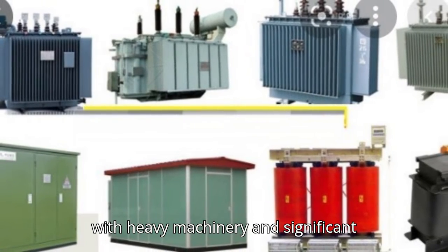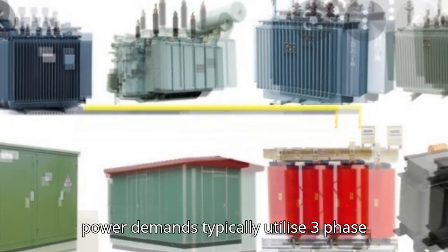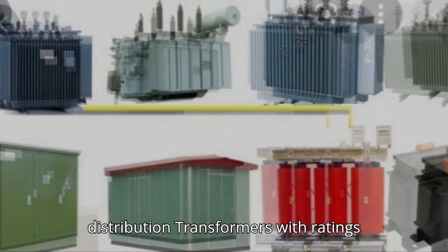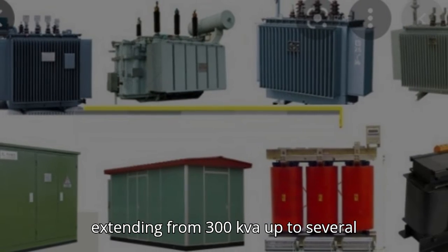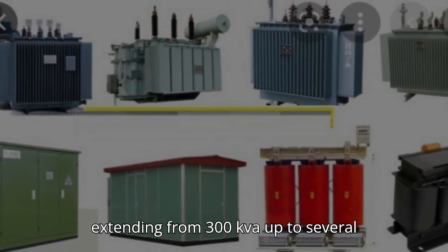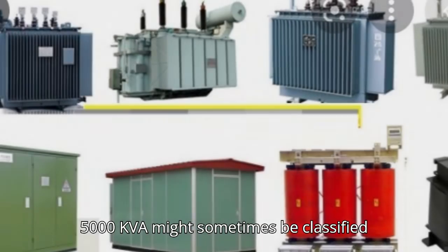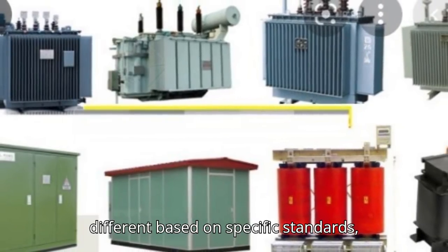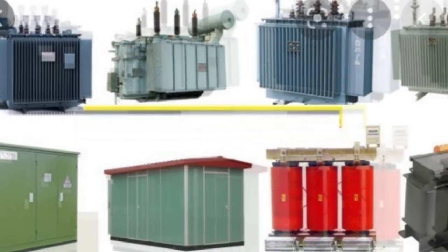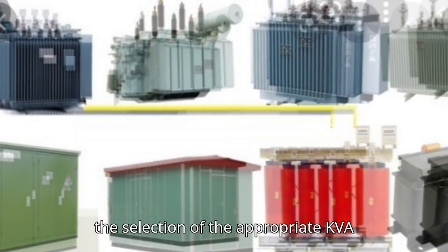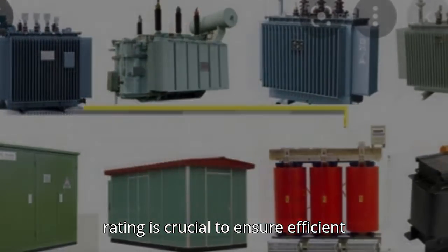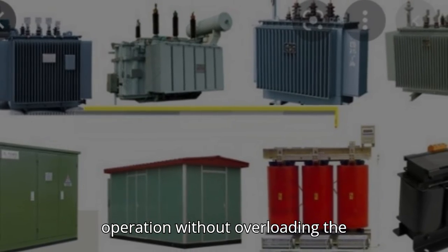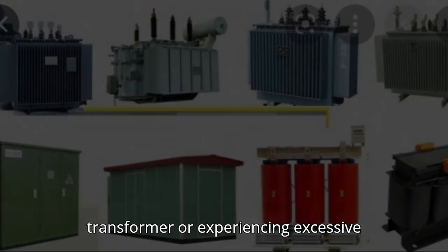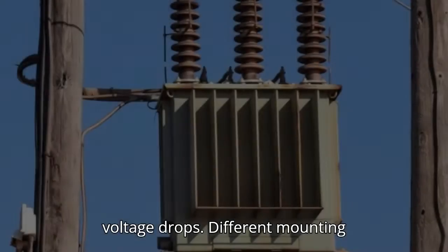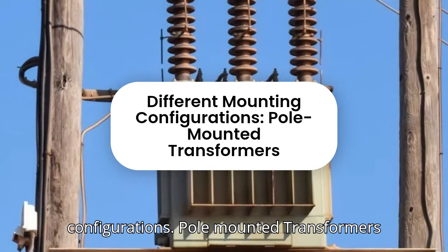Industrial facilities with heavy machinery and significant power demands typically utilize three-phase distribution transformers with ratings extending from 300 kVA up to several thousand kVA, although units above 5,000 kVA might sometimes be classified differently based on specific standards. The selection of the appropriate kVA rating is crucial to ensure efficient operation without overloading the transformer or experiencing excessive voltage drops.